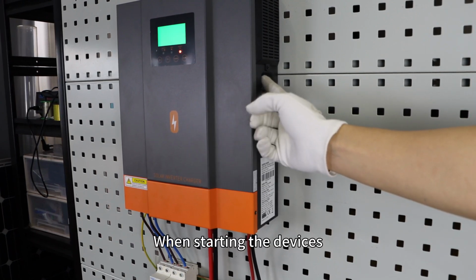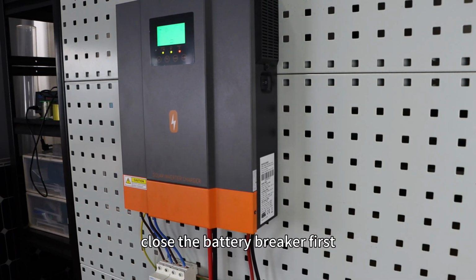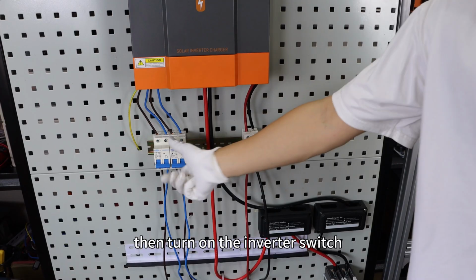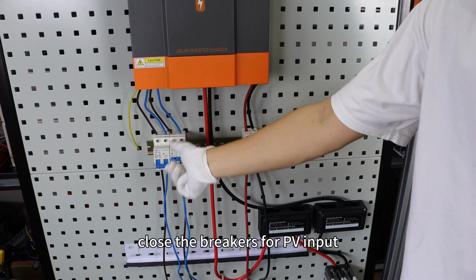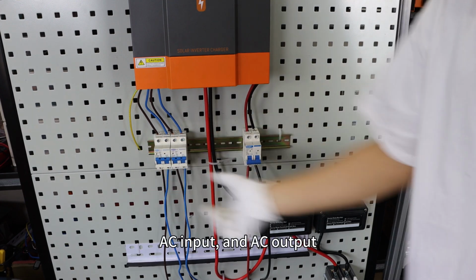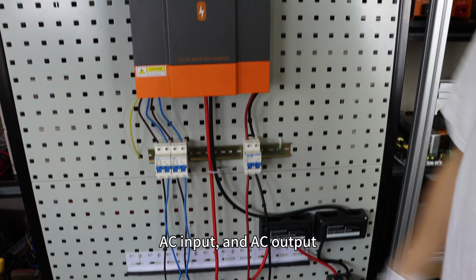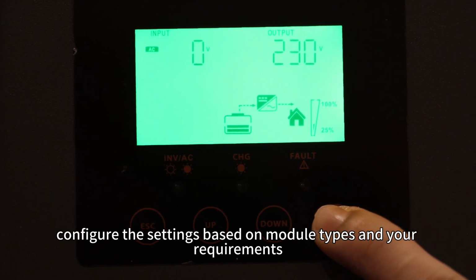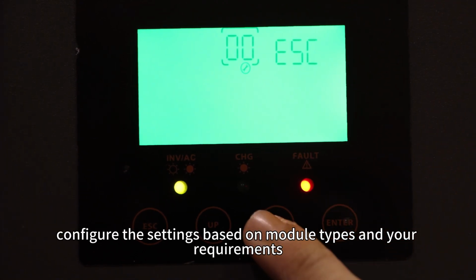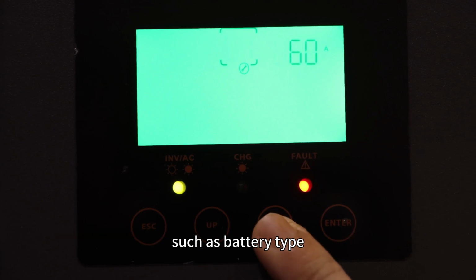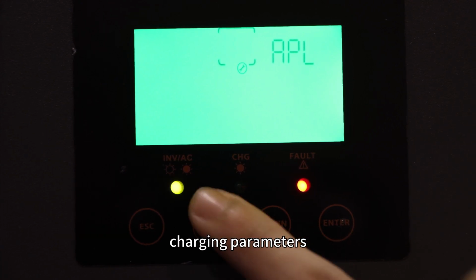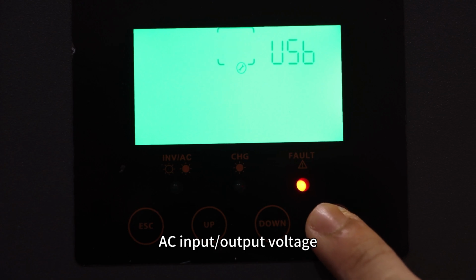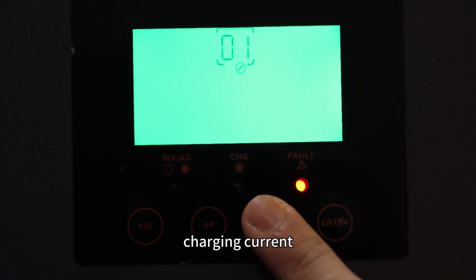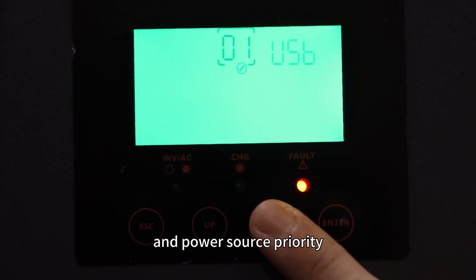When starting the device, close the battery breaker first, then turn on the inverter switch. Afterward, close the breakers for PV input, AC input, and AC output. After startup, configure the settings based on module type and your requirements, such as battery type, charging parameters, AC input or output voltage, charging current, output priority, and power source priority.